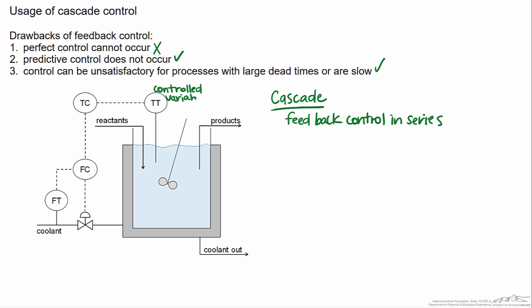And the reason why you want to control temperature in a reactor would be that it can be useful to prevent runaway reactions. It can also be a nice way to, based on doing a mass balance on the system, know what your products are going to be so therefore to get your system at its desired output. You have to set a particular temperature because temperature dictates reaction rate. So in this control scheme the manipulated variable is going to be the flow rate of coolant to the system. Obviously there is a whole host of other ways in which this could be manipulated, but for the sake of what we are doing here it is the flow rate of the coolant.